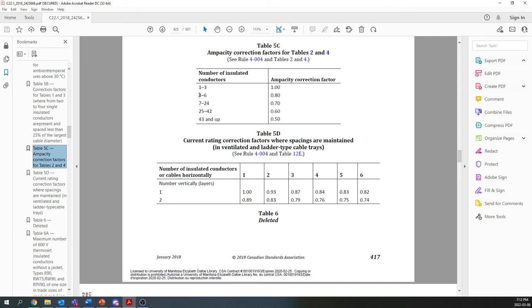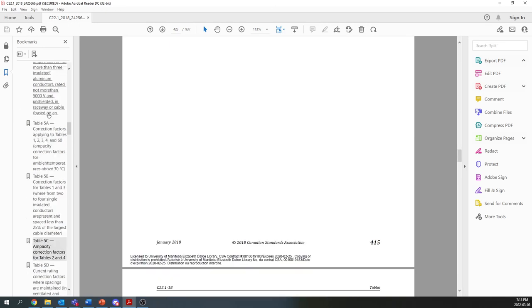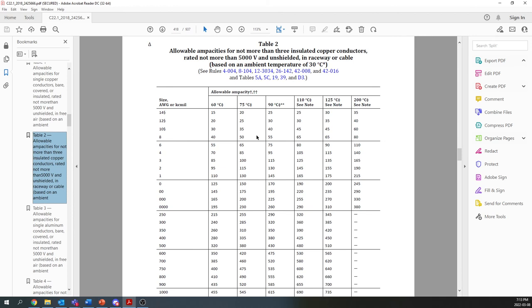The ground wire that we're going to pull in along with those other 5 wires doesn't count in this number here, because it should not, in a normal situation, have any current running through it. So it doesn't count. So actually, we have to apply a further 80% correction factor, 20% derating to our table. So now we have 77.35 times 0.8, which is going to be 61. That's way down.